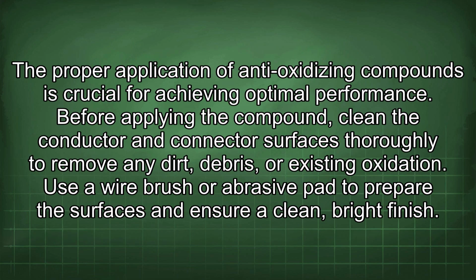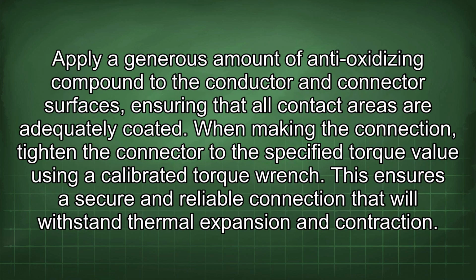The proper application of anti-oxidizing compounds is crucial for achieving optimal performance. Before applying the compound, clean the conductor and connector surfaces thoroughly to remove any dirt, debris, or existing oxidation. Use a wire brush or abrasive pad to prepare the surfaces and ensure a clean, bright finish. Apply a generous amount of anti-oxidizing compound to the conductor and connector surfaces, ensuring that all contact areas are adequately coated. When making the connection, tighten the connector to the specified torque value using a calibrated torque wrench. This ensures a secure and reliable connection that will withstand thermal expansion and contraction.